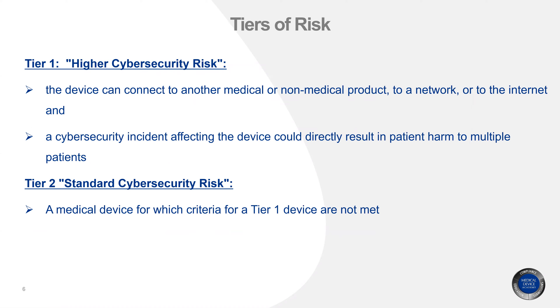Cybersecurity risk also has tiers of risk, taken from the FDA's draft guidance. Tier one is high cybersecurity risk — the device can connect to another medical or non-medical product, network, or internet, and if there is a cybersecurity incident, it could directly result in patient harm or affect multiple patients. Examples include pacemakers, dialysis devices, and insulin or infusion pumps. Tier two is standard cybersecurity risk — any device not defined by the tier one definition falls under tier two.